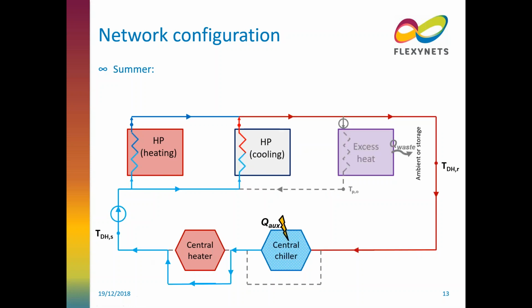Similarly, in summer where your main demand might be cooling, the main purpose here would be having a supply line here and then inject your excess heat from the cooling processes into the return line. In this case, your excess heat will not be injected, so that's just wasted, and you might need a centralized chiller instead of a centralized heater.